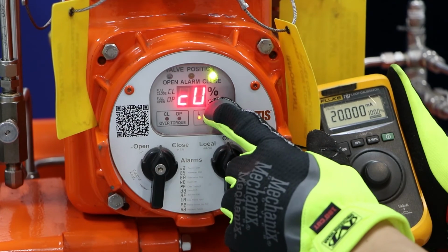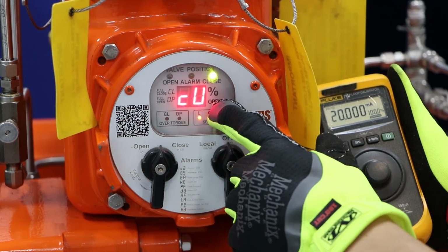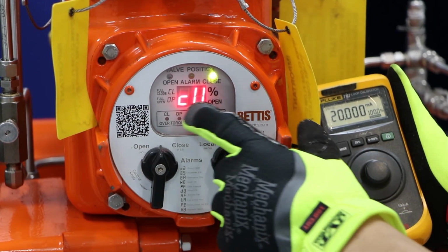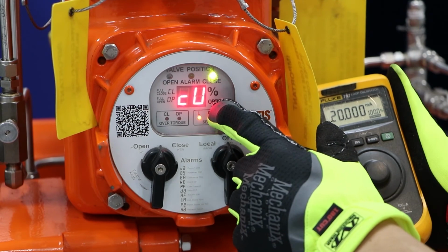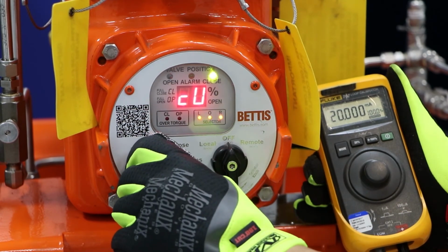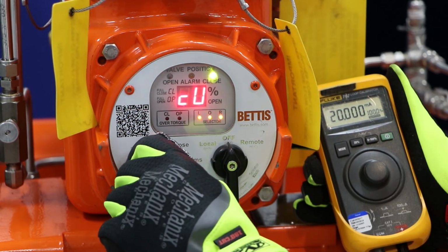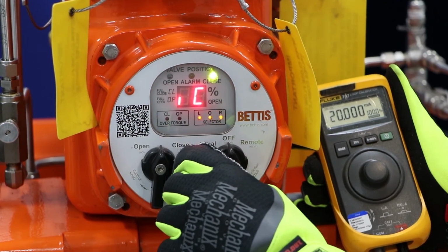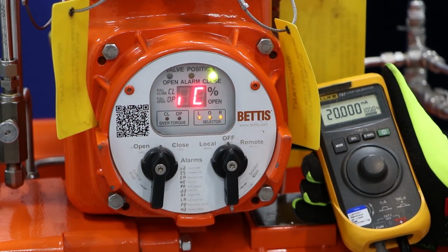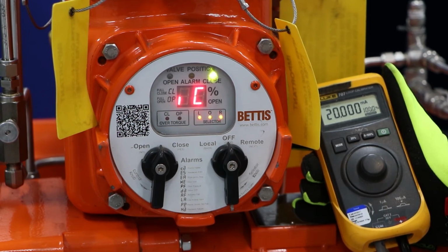And you see CU. CU means you passed. If you failed, you'll see CF, and you have to do this again. So if we passed, we'll go ahead and hit yes. At this point, if we see IC, it means we've successfully set our analog calibration for both the lower limits and upper limits. What you can do is save the settings and exit the menu now.